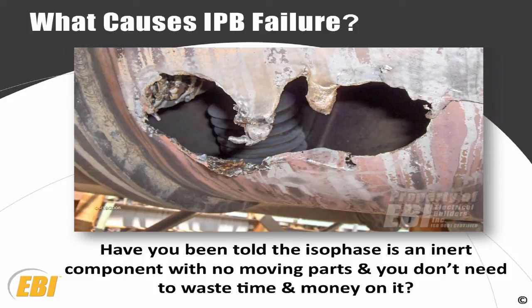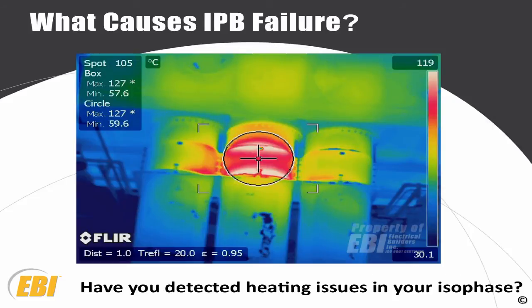A lot of times the people at the plants will take an attitude toward isolated phase bus that it has no moving parts. It'll last forever. It will, until it blows up. A lot of times when you look at your bus with an infrared camera, you will see hot spots like this one here. This one probably has connection problems on the bolted covers that are shown there, where you see the heat. It's not allowing the ground currents to pass the way they should.